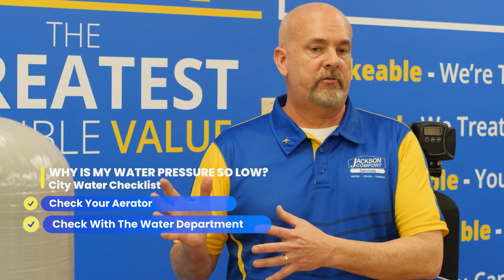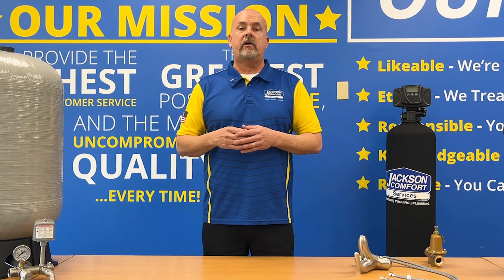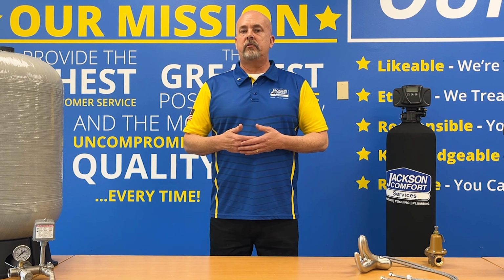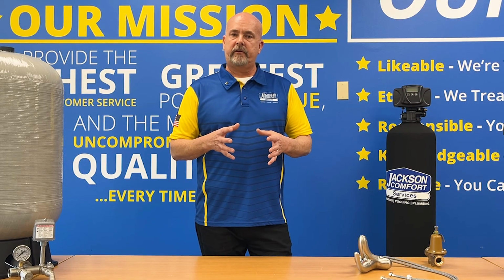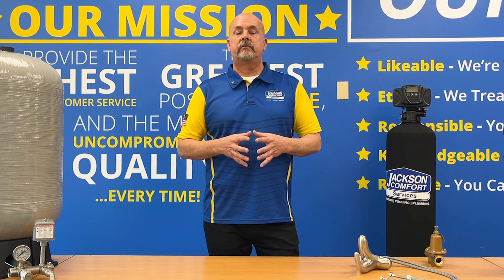They may be having some issues with their pumps. They may be having a water main break somewhere, which is causing low pressure in the neighborhood. And so the first phone call should really be to the water department. After that, pretty much everything inside the house besides the water meter is your responsibility in Northeast Ohio where we are. So there are some devices that are installed that could cause some lower water pressure or some pressure issues. A lot of times the water pressure provided to the home is way too high.